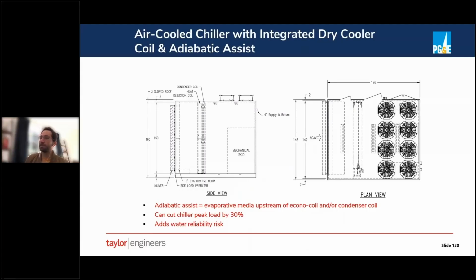And then here's another option that adds just a little bit more complexity to the system concept, where we're putting an evaporative pre-cooling coil upstream of the dry coil. What this is doing is allowing us to not fully approach wet bulb the way we would with a true waterside economizer, but it's depressing the dry bulb temperature of the ambient air that's hitting the economizer coil, and in doing so, increasing the amount of economizer hours that we get out of the system.